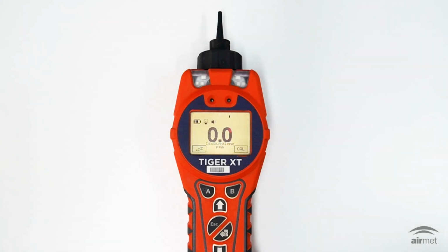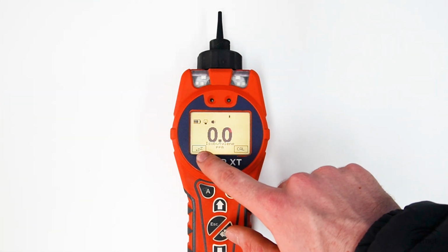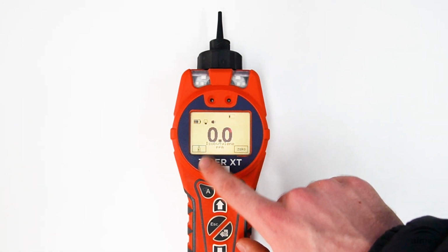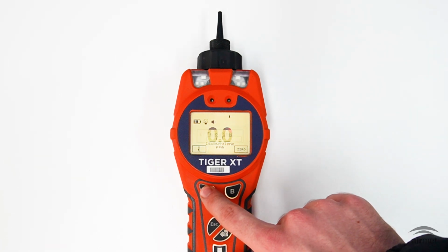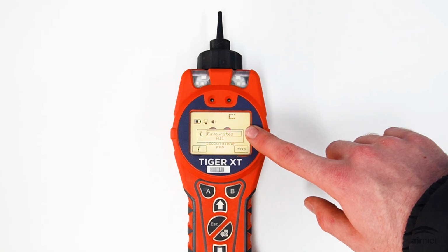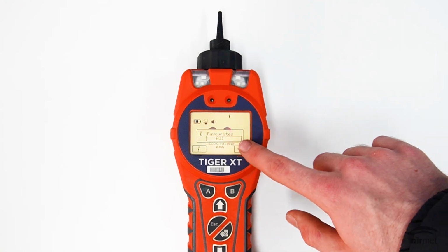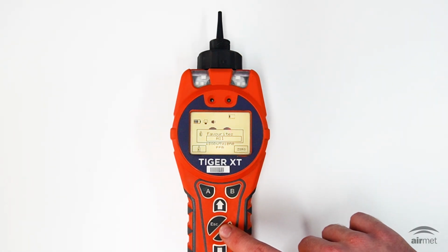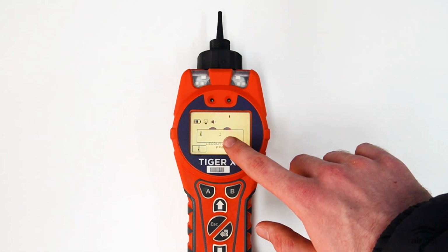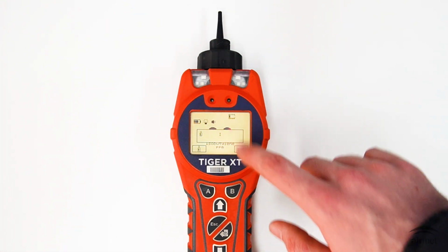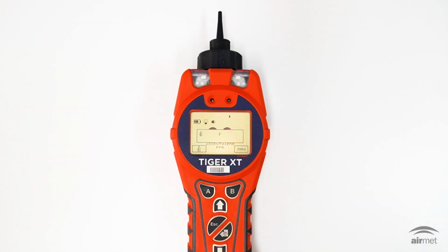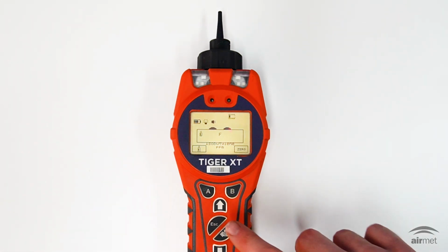To change the reference VOC gas on the device, use the up and down soft keys until you navigate to the calibration gas icon. Once you have the calibration gas icon, press the A soft key to enter the menu. From here, you can either select from a list of saved favorites or all reference VOC gases listed. Press Enter to confirm your option. Next, scroll through the alphabet until you reach your desired VOC gas. Once the letter shown matches the first letter of your reference VOC gas, hit Enter to confirm.